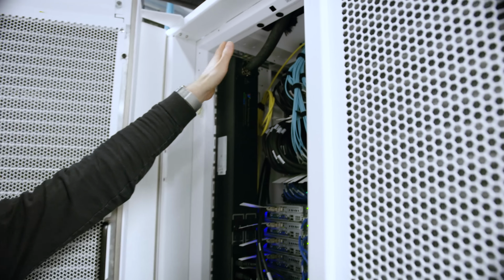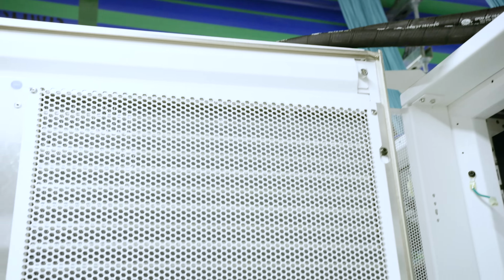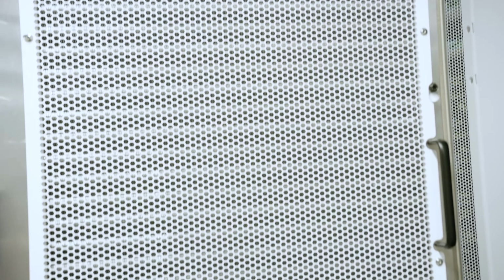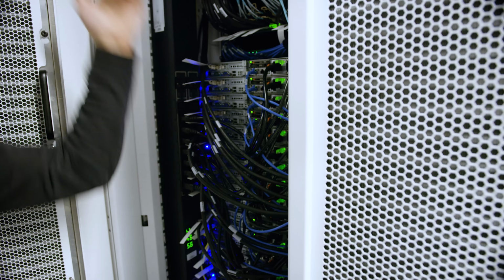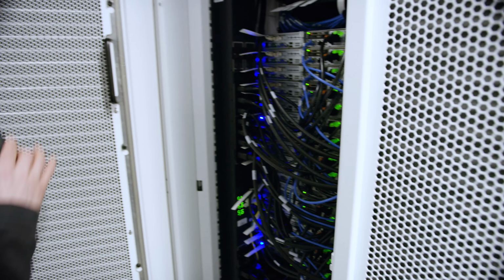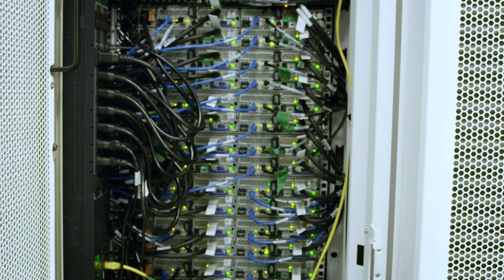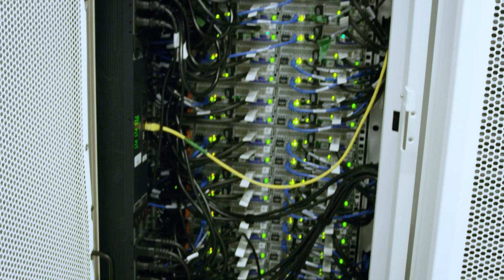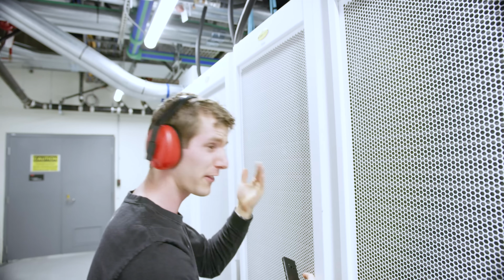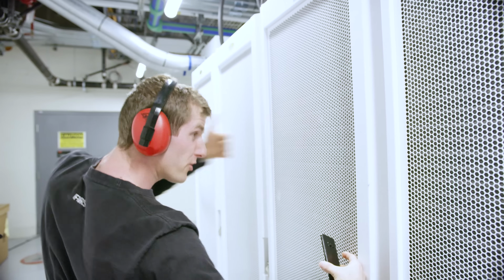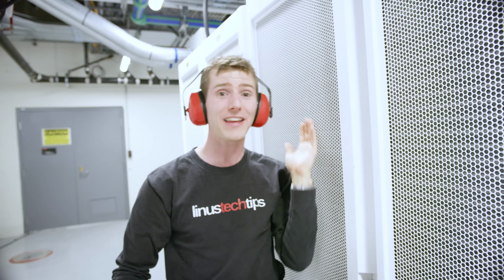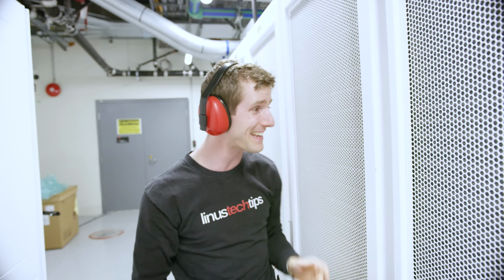What they're doing is they've just got the fronts of the racks all sealed up so there's no backdraft pressure, and they've got normal air-cooled servers that pass the air from the front, where they just draw in room temperature air in here and it comes out hot, like 30 plus degrees, and push it through this heat exchanger where it is actually cool to my skin. That's how efficient these are.